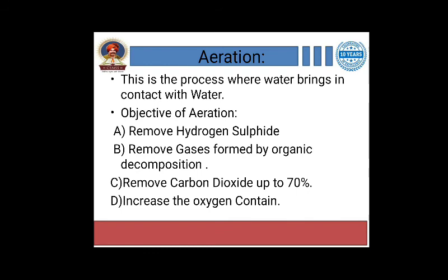Right? Objectives of aeration: to remove hydrogen sulfide, remove the gases formed by organic decomposition, and remove carbon dioxide up to 70%. It means aeration will remove carbon dioxide up to 70%, and again it increases the oxygen content.